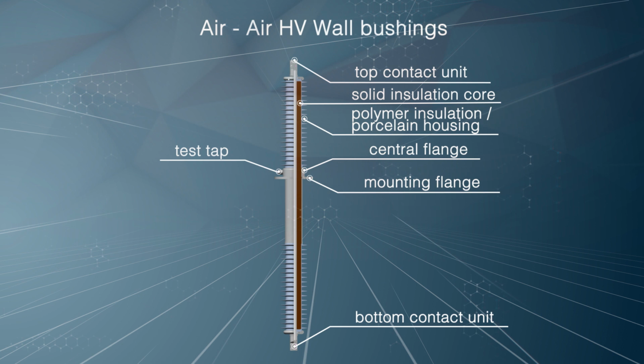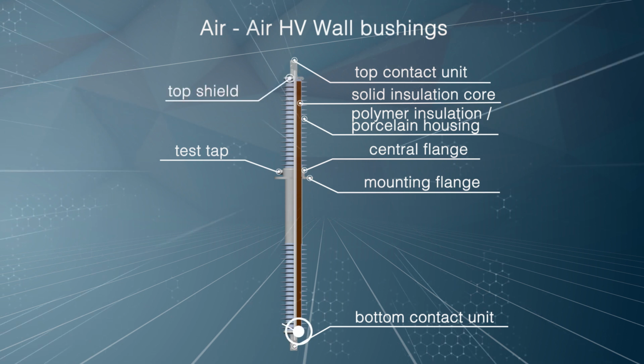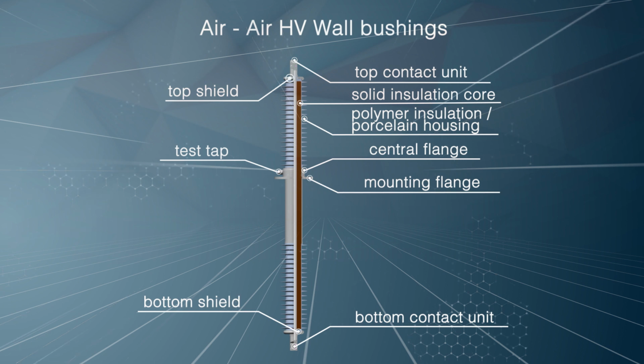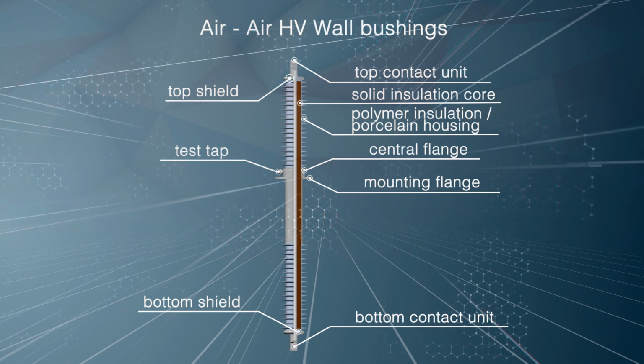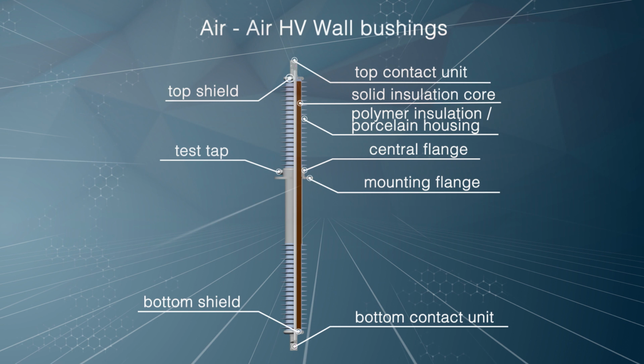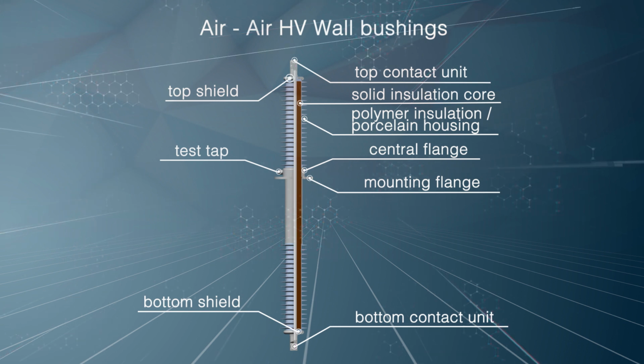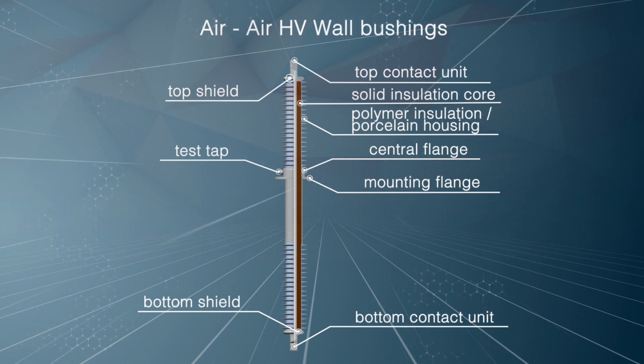Shields are used in bushing designs with polymer external insulation and are used for equalizing the external electric field in the top and bottom parts of the bushing. In bushings with porcelain housing, the function of the shields is performed by the top and bottom flanges.